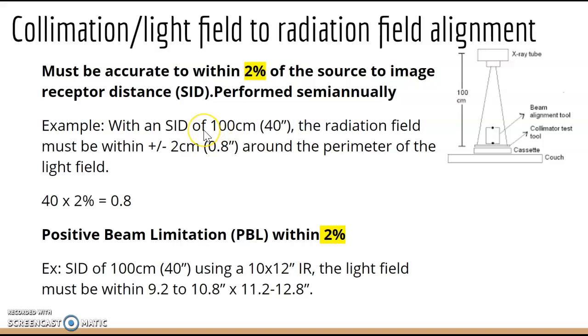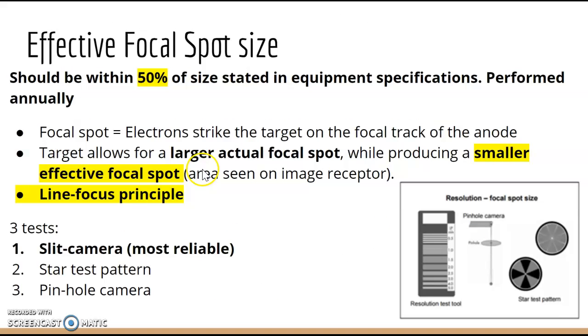PBL — Positive Beam Limitation — is when you insert a 10x12 cassette in a Bucky and the light automatically opens to 10x12. That's within 2%, same as the collimation tolerance. Effective focal spot size should be within 50% of what the equipment specifications stated.